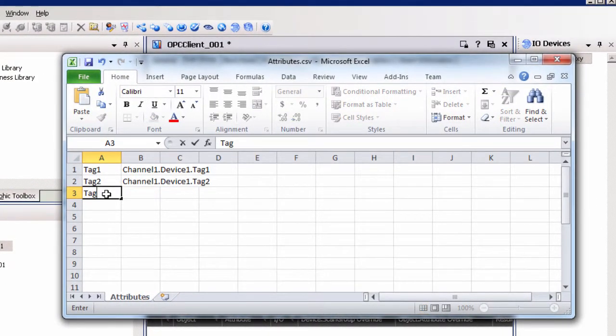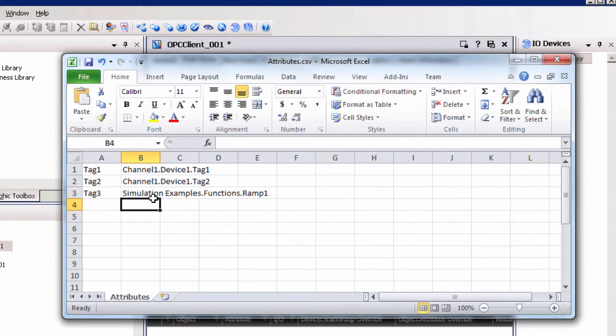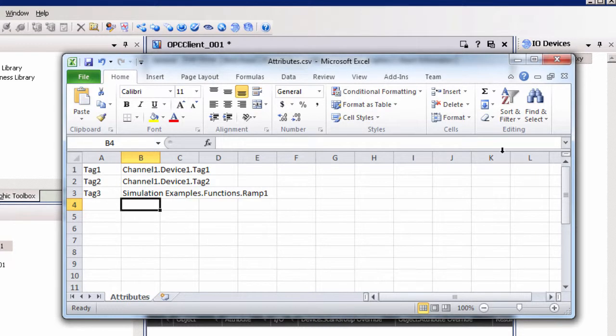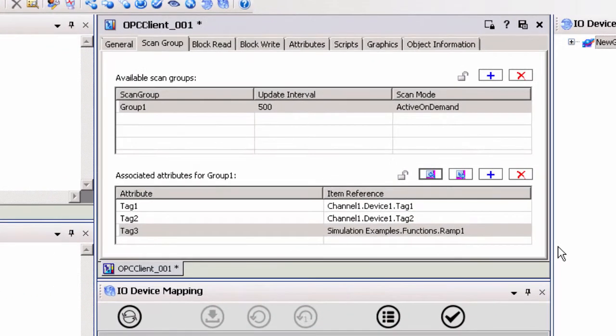We can now add more items to the CSV file. Once the desired items have been added, save the CSV file and import it by clicking the import button next to associated attributes. Once the file has been imported, you will see the new items in the attributes list. If you have a static tag database in TopServer, you can take advantage of the CSV import and export feature in TopServer to export the tag list, make any required changes to fit the System Platform format, and import the list into System Platform.